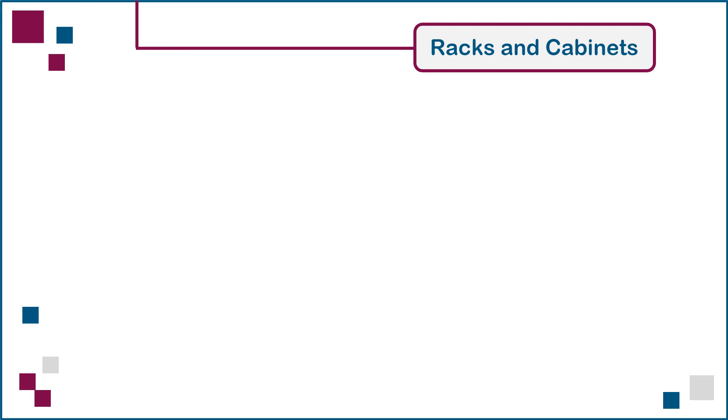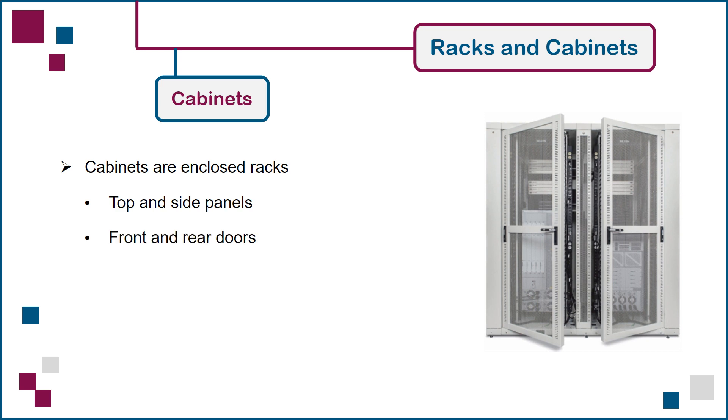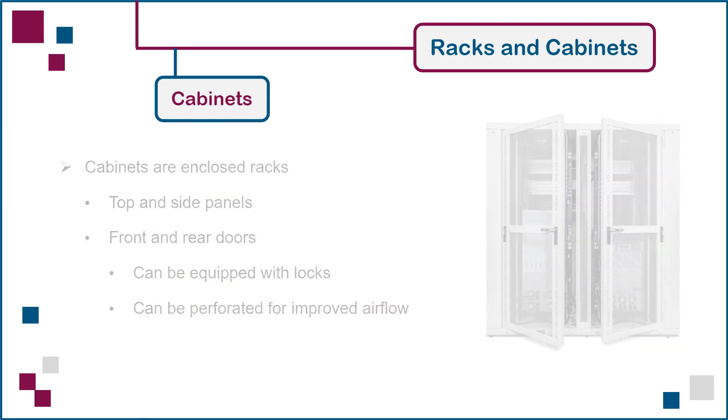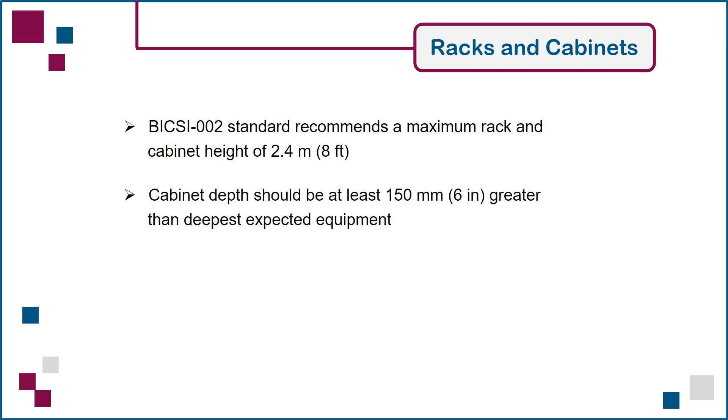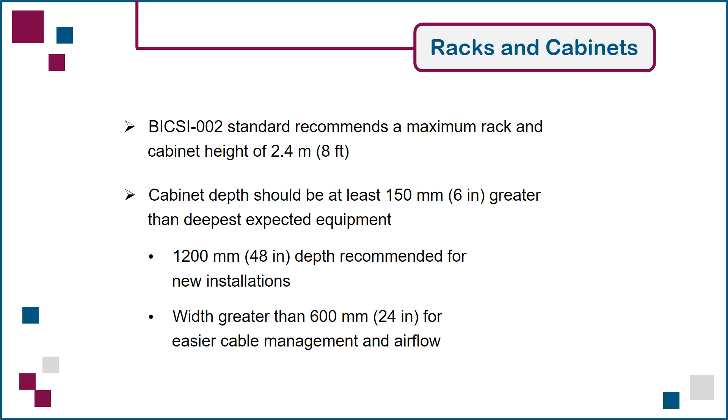An equipment cabinet can be described as a four-post rack with panels added to all six sides. The panels provide physical protection to the contents, as well as the ability to direct airflow into and out of the cabinet. They can be solid or perforated, with various openings to facilitate cable entry. The BICSI 002 standard for data centers recommends a maximum rack or cabinet height of 2.4 meters. For maximum flexibility, a cabinet should be at least 150 millimeters deeper than the largest device it is expected to house. Best design practices suggest allocating sufficient space for a 1200 millimeter depth. It's also recommended to consider cabinet widths greater than 600 millimeters in order to facilitate front-to-rear airflow and cable management.